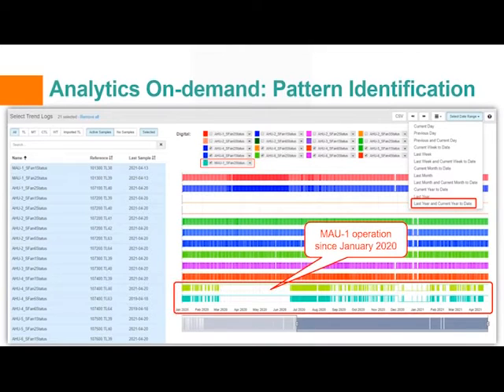The answer is yes. Let's start with the historical record and look at the supply fan operation since January 2020. We've now pulled up more than a year's worth of data, and we can quickly see that MAU1 doesn't necessarily always run 24/7, but there have been periods when it has. In this case, we can see that the fans have been running continuously since the beginning of March till the end of June. From here, we can further drill into this time frame to better determine why the fans were always running. We can also display additional data points that we know are relevant to this unit and that will assist us in identifying the cause of this fault. We'll continue on with this example on the next slide.